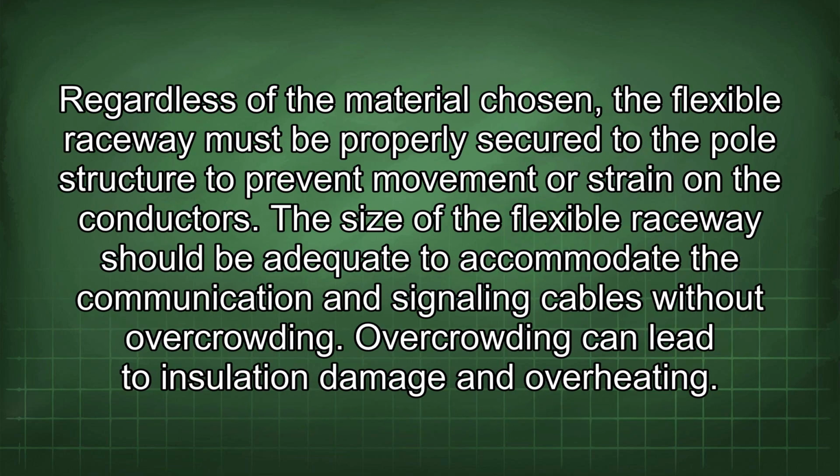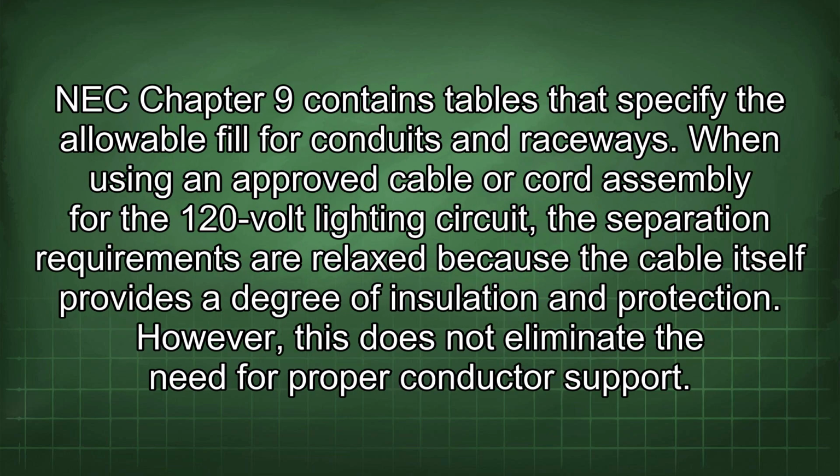Regardless of the material chosen, the flexible raceway must be properly secured to the pole structure to prevent movement or strain on the conductors. The size of the flexible raceway should be adequate to accommodate the communication and signaling cables without overcrowding. Overcrowding can lead to insulation damage and overheating. NEC Chapter 9 contains tables that specify the allowable fill for conduits and raceways.